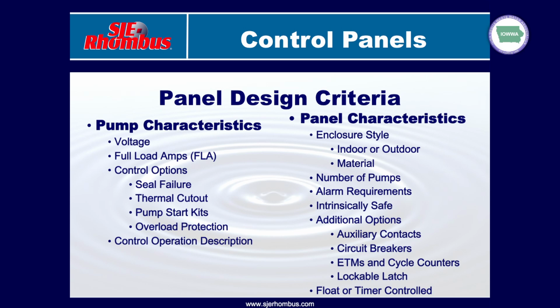We need to know if it's going to be installed indoors or outdoors, so we get you the right NEMA rating on the enclosure. Number of pumps, in so far as a standard product that we manufacture, if it's in our catalog, we do a maximum of 2 pump or duplex panels. But on the custom side of the street, we can build a control panel to operate as many pumps as you guys can dream up or the engineer can dream up. Intrinsically safe circuitry, again, we can build that into the panel.